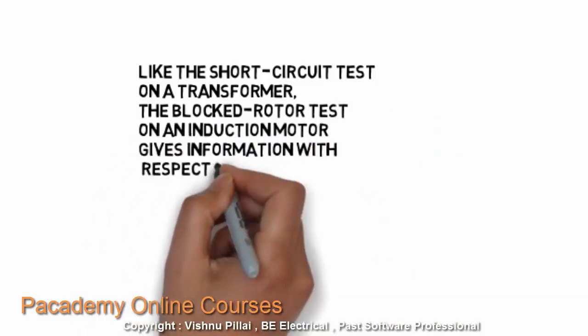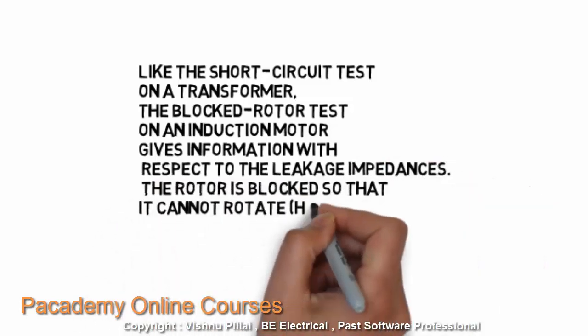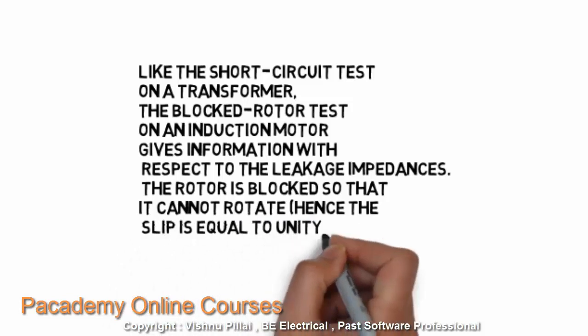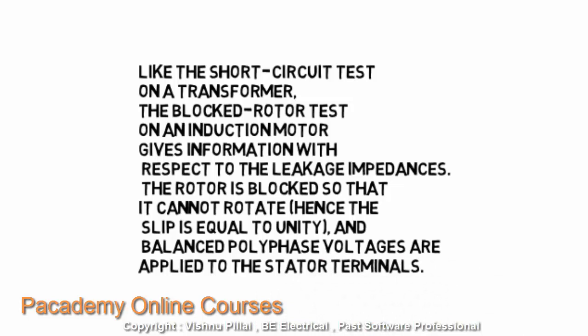Like the short circuit test on a transformer, the blocked rotor test of an induction motor gives information about leakage impedance. The rotor is blocked so it cannot rotate, making the slip equal to unity. Balanced three-phase voltages are applied to the stator terminals. This is analogous to the short circuit test of a transformer where the secondary was shorted — here the rotor (the secondary equivalent) is blocked, creating an ideal short circuit condition.